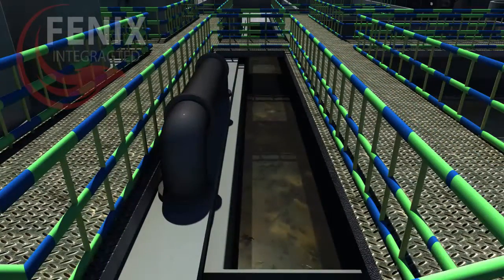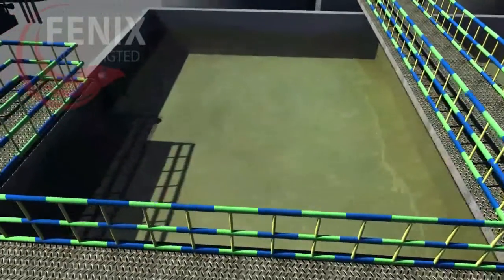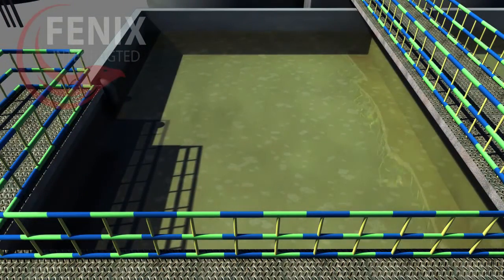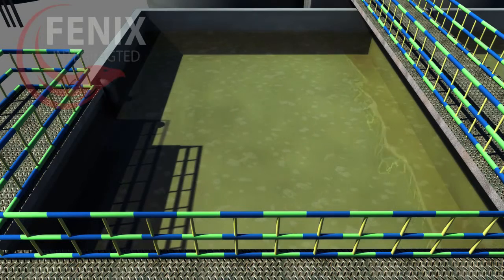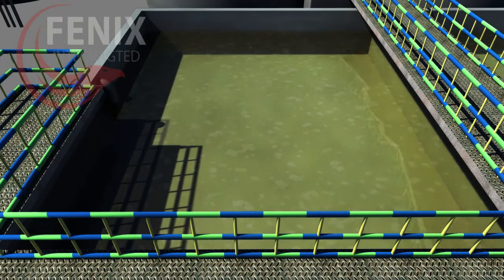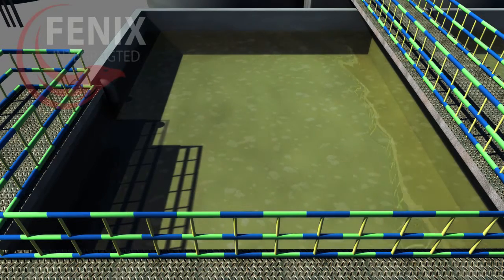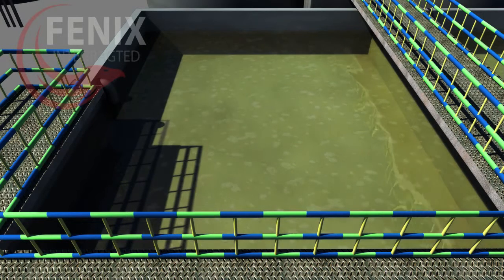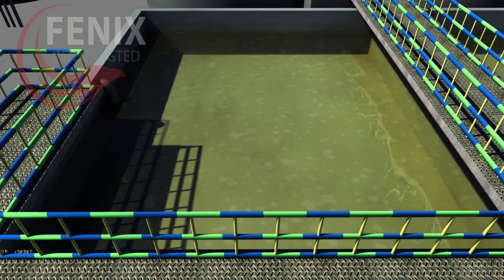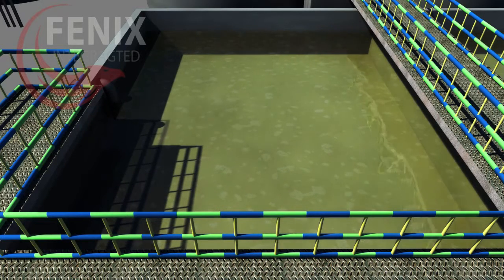Now that the wastewater is cleared from the solid elements and grease, it's time to clear it from bacteria, and so it moves into the biological treatment tank. Here we have very tiny bugs that will do the job of cleaning the wastewater from bacteria by eating them. These tiny bugs are too small to be seen with the naked eye, and they clean wastewater by eating the waste in it and converting it to nitrogen gas, carbon dioxide, and other gases. They do this continuously, and we need to supply them with air to survive. That is why air blowers are used in the biological treatment tank.